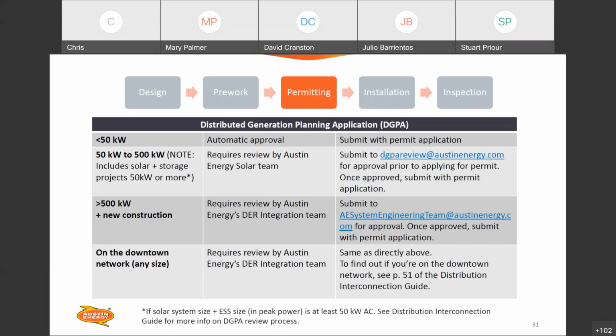If it is more than 500 kW or new construction, this requires review by our DER integration team — please submit to the AE System Engineering Team email shown. That usually requires some additional legwork on their end. There's also an interconnection agreement in our distribution interconnection guide generally required for those 500 kW and above projects.